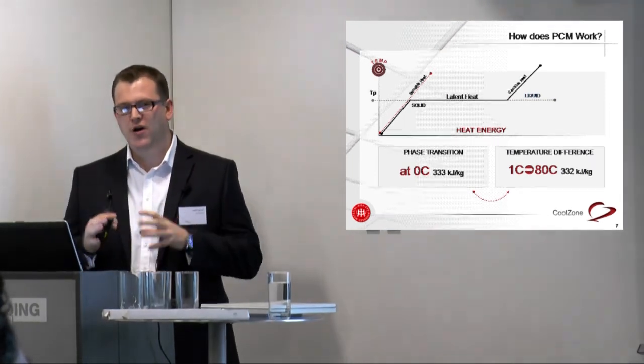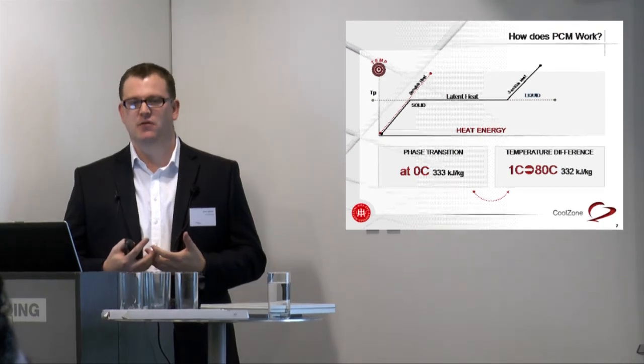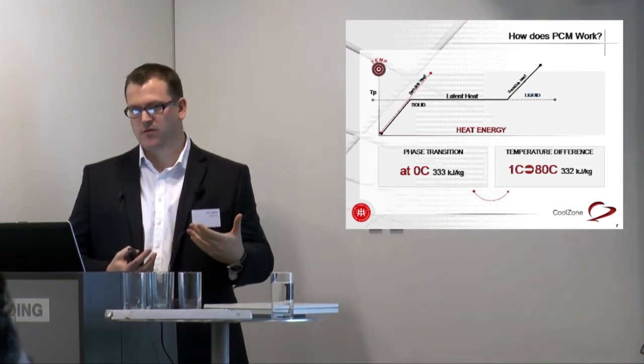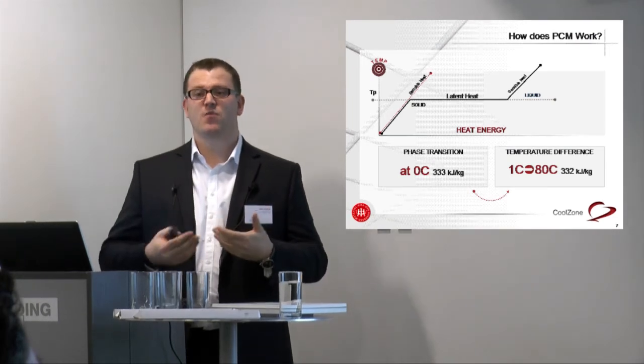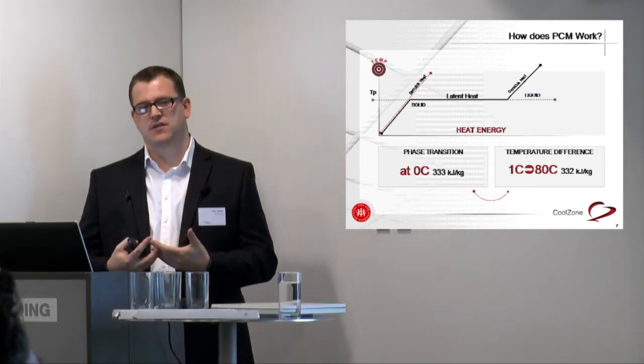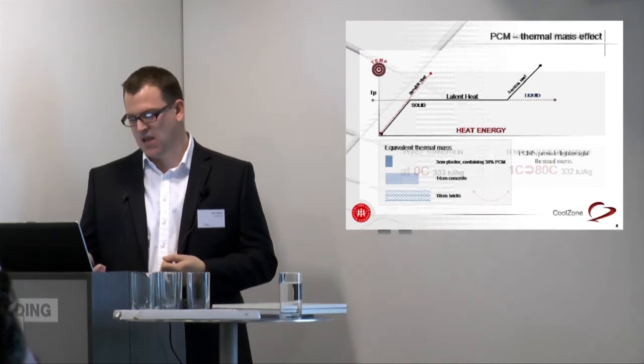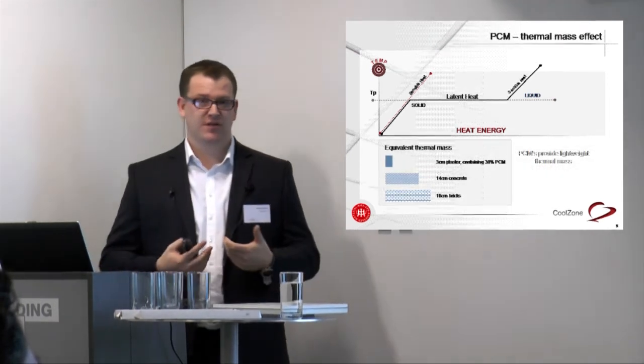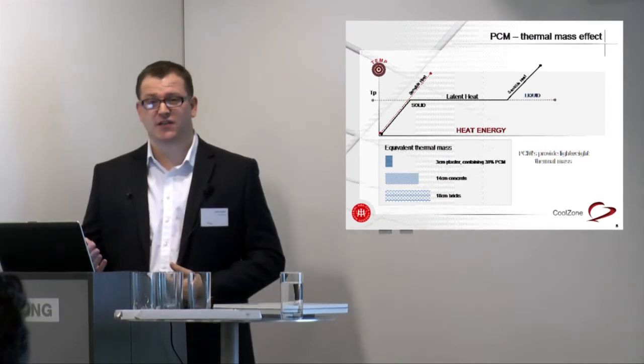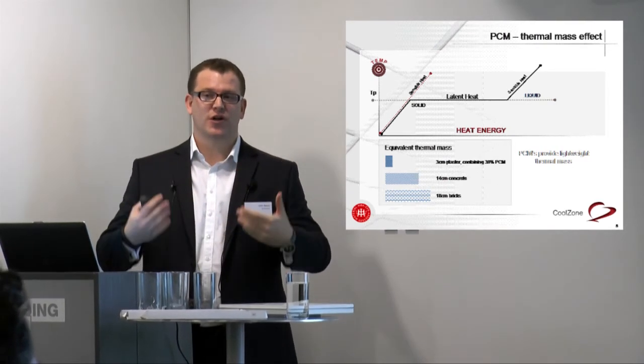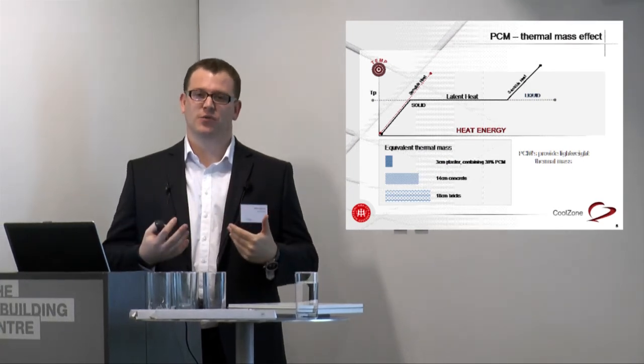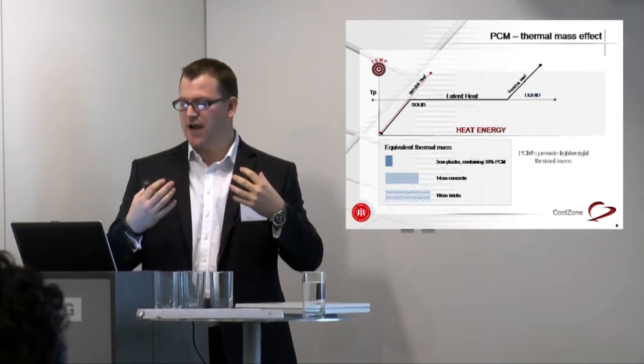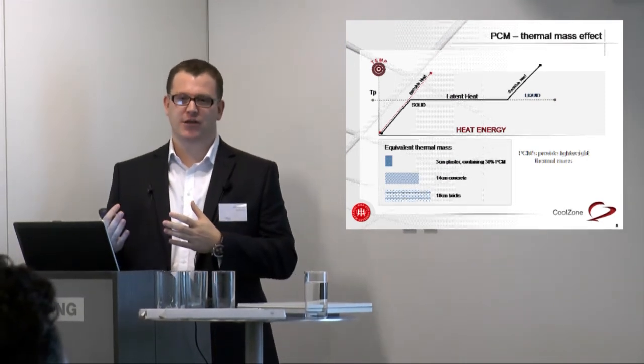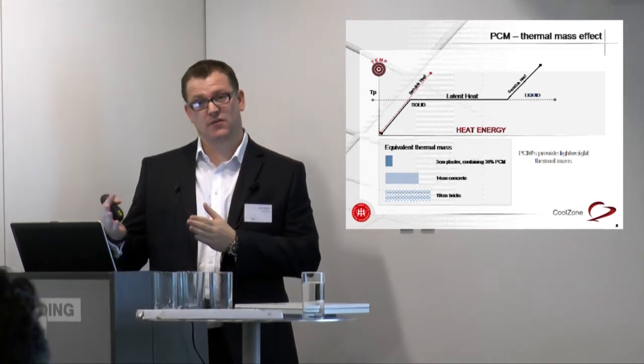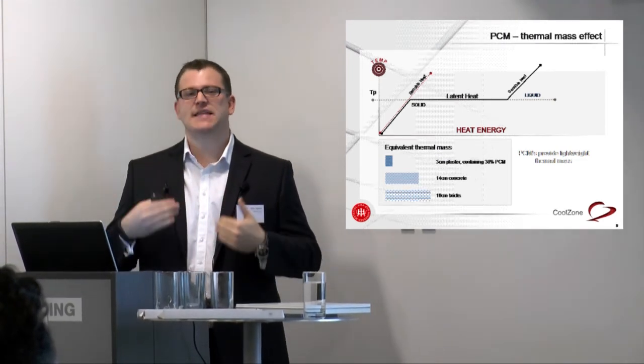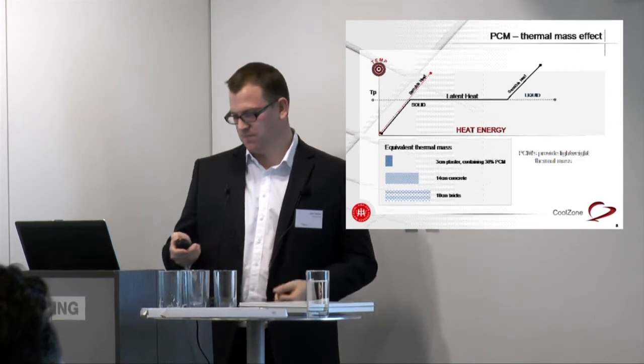If we get to a point where we can't do that, we just have an expensive ceiling tile—we get absorption of heat on the first day, but if we can't reset the tiles, they never get a chance to absorb again. So if we have areas in constant use, potentially a data centre or A&E in a hospital, where there's a constant heat load, PCM would not be suitable. We need that couple of hours of absorption to delay your air conditioning, or in some cases negate the requirement for it, but we need that downtime to let the heat drop back out of the product.